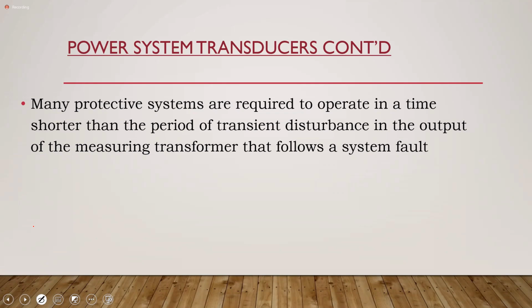So the point we are making here is that the protection system may need to operate in a much shorter time than when the transient itself exists on the system. You with me? And so it's important that the transducer is able to faithfully represent what is on the system, because once that information reaches the relay, then the relay, based on how it is set up, will have certain decisions to make. And so we are dealing with a time-sensitive thing.